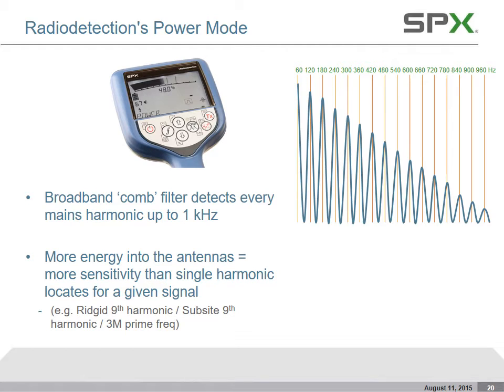So there is an enhanced power mode on this new locator. You still have the basic power mode that will pick up all the harmonics from 60 Hz up to 960 Hz. Anything that's divisible by 60, it's going to pick up. The only bad thing about that is when you get in an area that's very congested around a transformer or a switchgear or a substation, you might need to filter out some of that information in order to get good depth readings and a better locate, a much more precise locate.